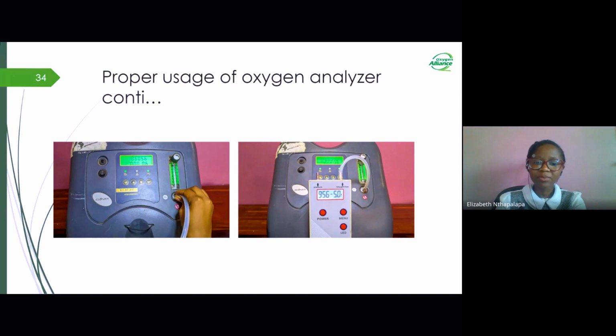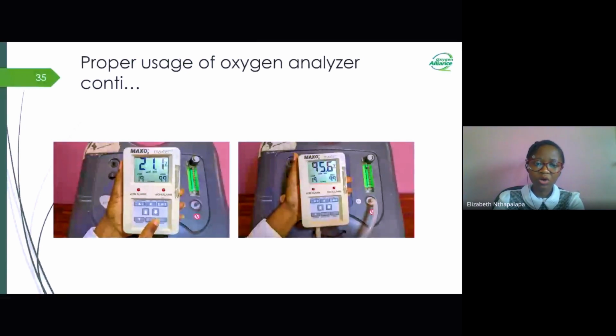And after letting it stabilize, we're going to see that our oxygen analyzer is giving us the figures of the oxygen purity. For example, here this machine is giving us 95.6% oxygen purity at 5 liters. And I'll also do a quick demonstration of the electrochemical oxygen analyzer. The same things: we switch it on, and it will start displaying the oxygen purity at 21%. And this one has different thresholds, as I mentioned at some point, the lower threshold and the upper threshold. After connecting it securely to the oxygen concentrator, it is also giving us the oxygen purity at which this machine is producing the oxygen.